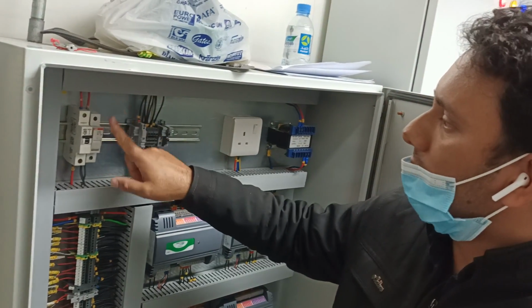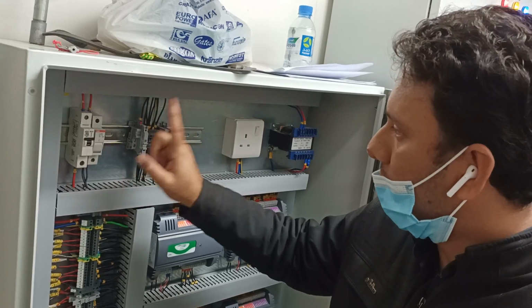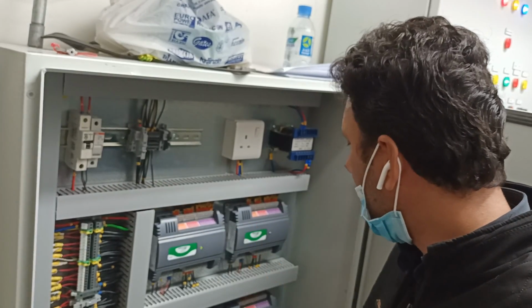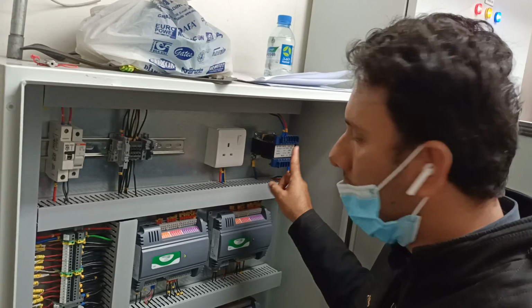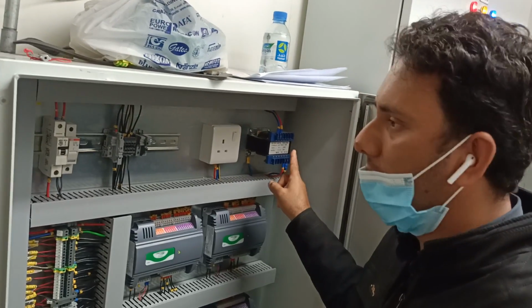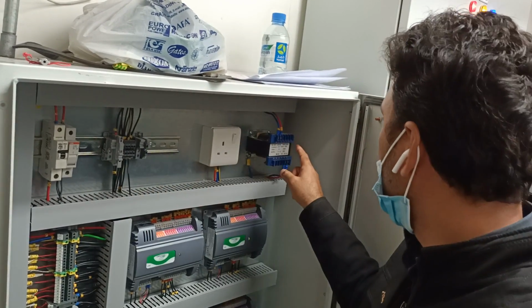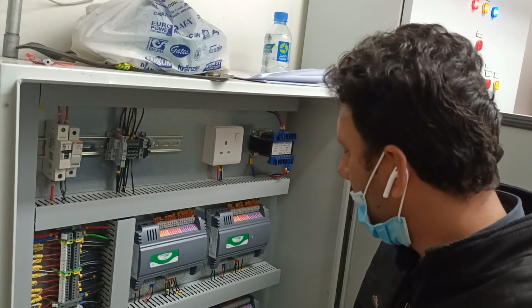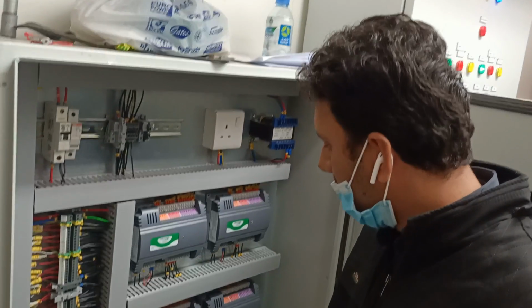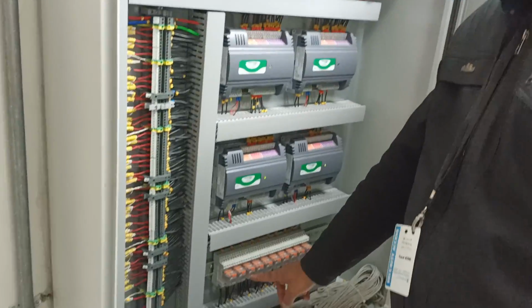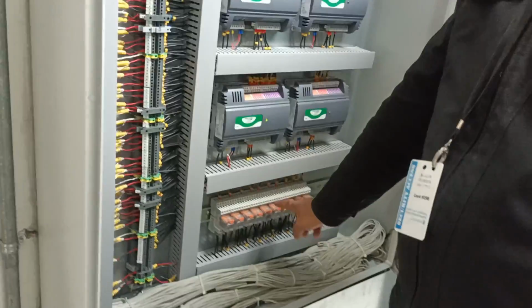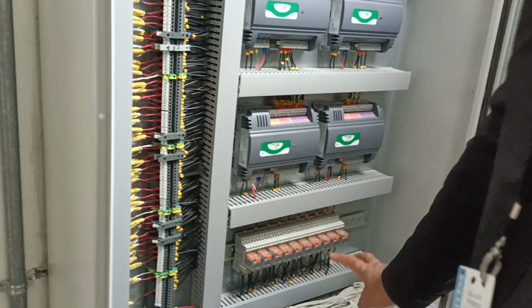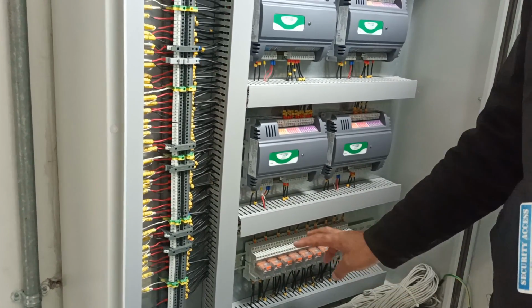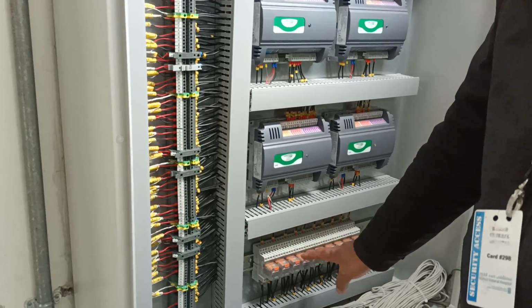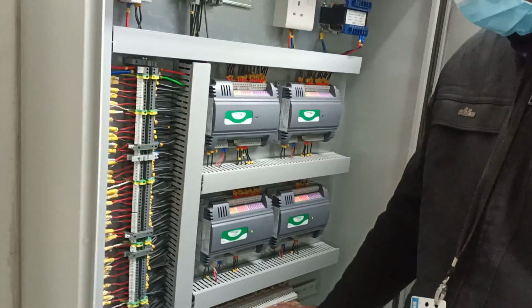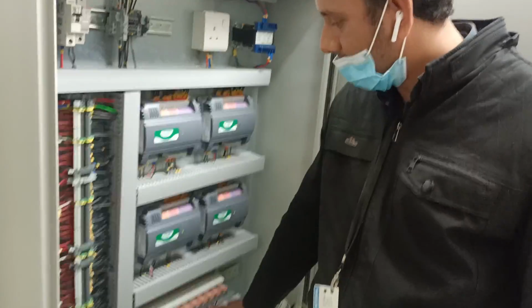So the power supply is coming to this breaker, and if these controls are 24 volt, then definitely a transformer is required. So from the AC it goes to the transformer, and from here it feeds the relays and the controllers. Here you will see there are some relays. These relays are dedicated for actuators. I will show you the drawing, in which you can see how many actuators are installed, and for that these relays are used.